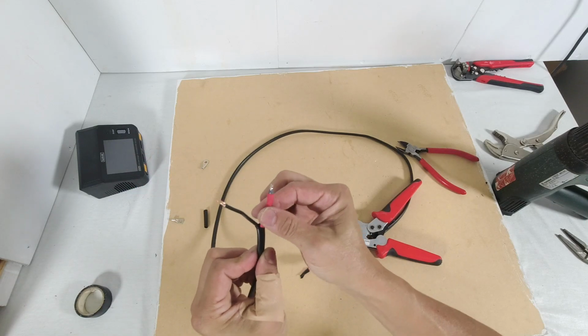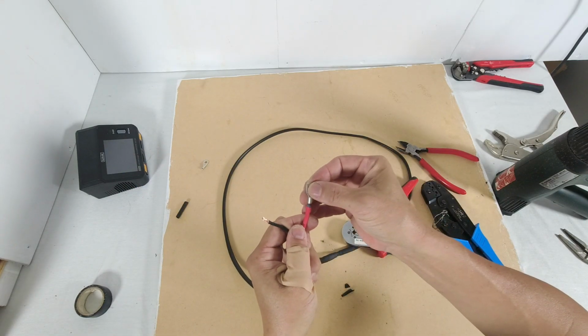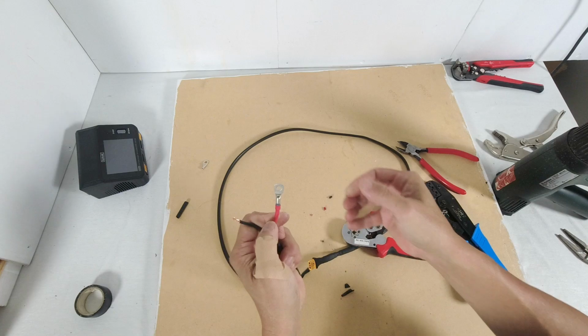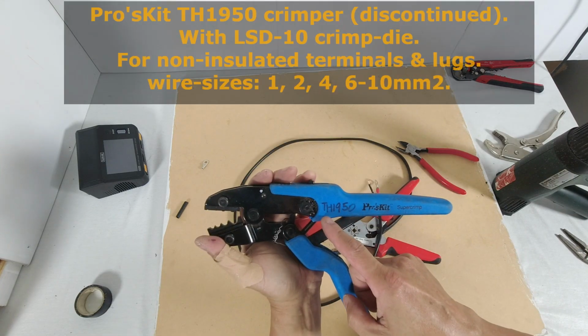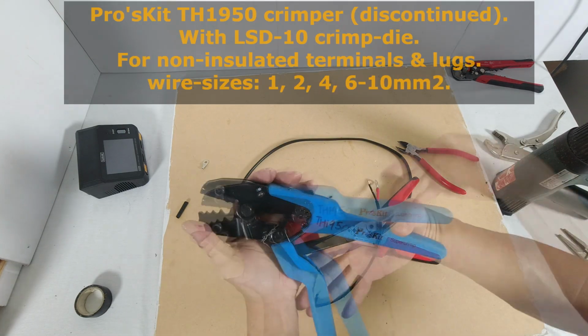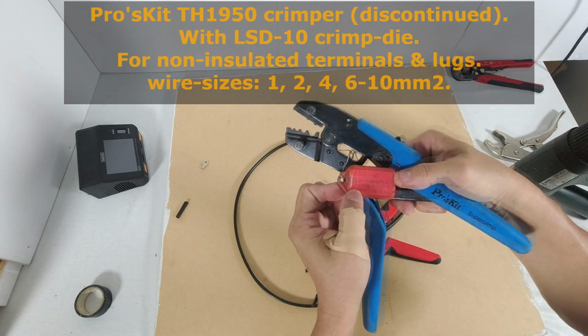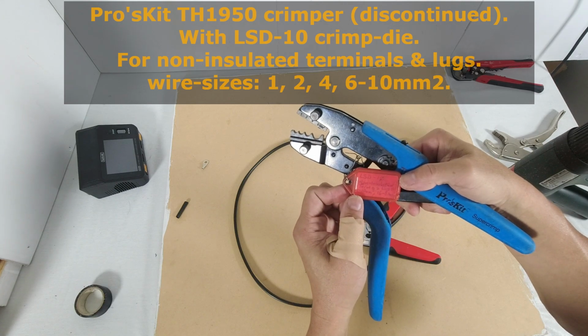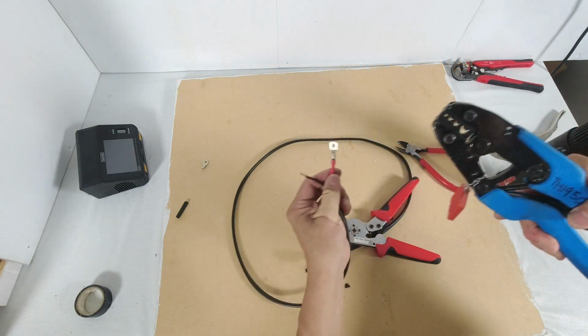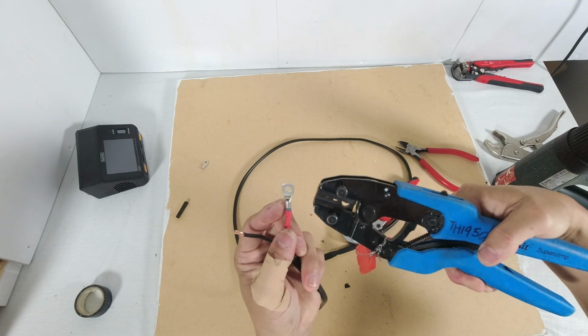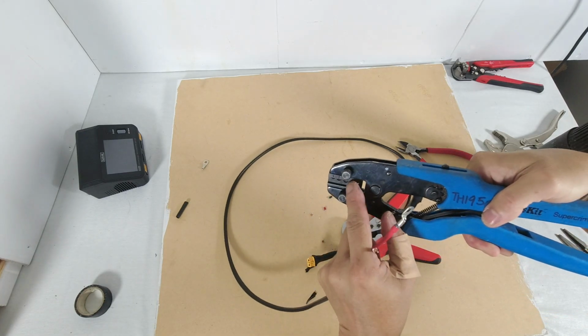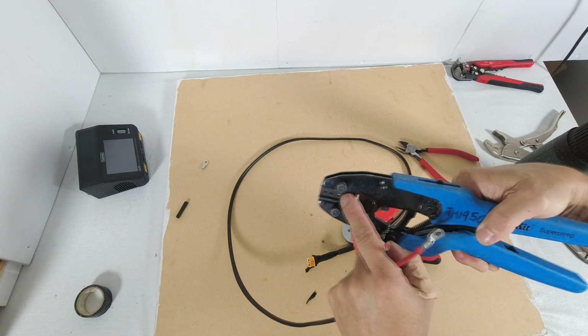That's done. Insert the copper lug, goes in there. This is my Pro'sKit TH1950 crimper. I have a crimp die in here, it is LSD number 10 for non-insulated terminals and lugs, ranging in size from 1 to 10mm square. This lug is for 4mm square wire, so I will crimp it using that number 4 die.